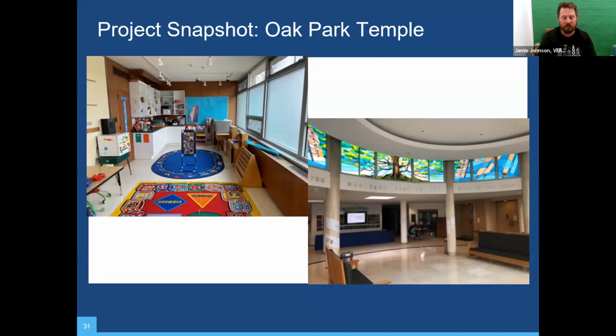One of the things that really struck me about this building was that during COVID, in order to stay open, there's a preschool with about 20 classrooms. Not all are occupied, but they're used six to seven days a week. They had to leave their windows open year round, winter, cold, polar vortex, 100-degree days, two windows open in each classroom, to have adequate ventilation to meet state requirements to remain open, because there was zero outside air coming into the school. There was very limited outside air coming into the main sanctuary area and community center we saw earlier.